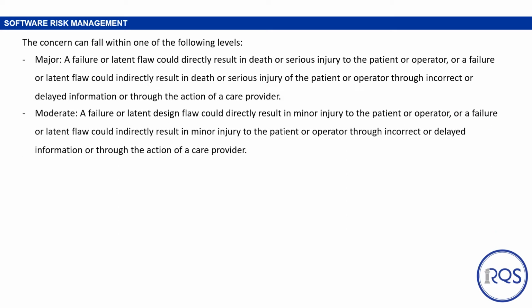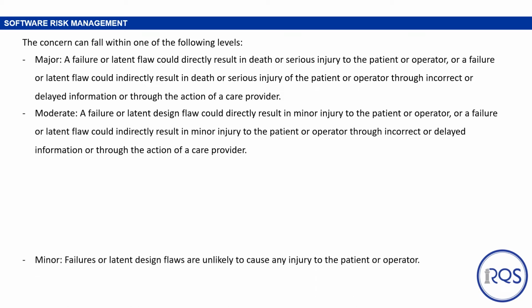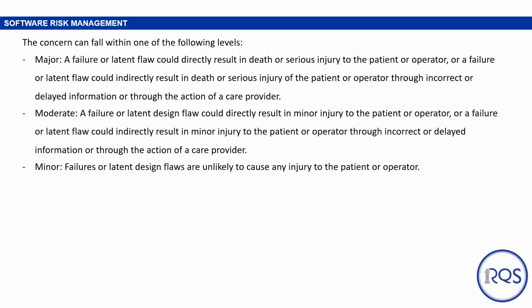With moderate level of concern, a failure or latent design flaw could directly or indirectly result in a minor injury to the patient or operator through incorrect or delayed information or through the action of a care provider. And with minor level of concern, failures or latent design flaws are unlikely to cause any injury to the patient or operator.